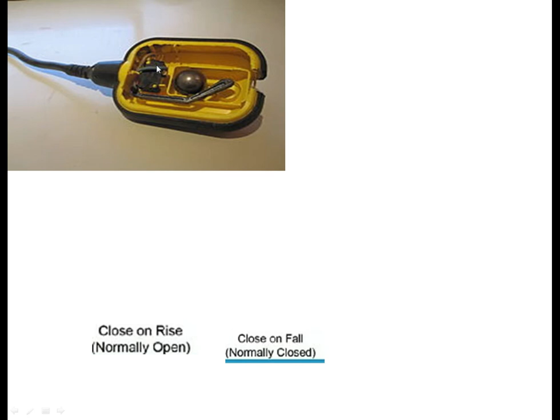See, this float sensor closed means it is in NC position, and this is in NO position. When you see this water level indicator, this is the normal position when your tank is getting filled. After filling, it becomes like this, meaning it will flow from lower to higher rise. This weight we are putting will float in the water, and when it senses up to here, it will float and send a signal to the motor, meaning you have to turn off the motor or alarm.